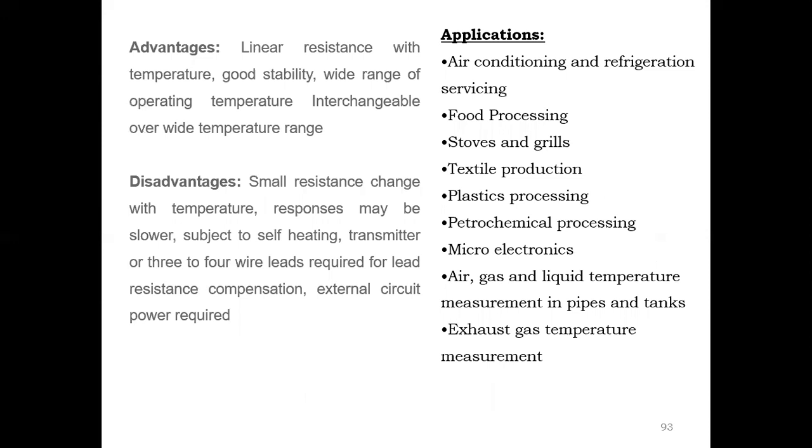Advantages of the RTD: linear resistance with temperature, good stability, wide range of operating temperature, and interchangeability over a wide temperature range. Disadvantages: small resistance changes with temperature, responses may be slower, subject to self-heating, and three or four wire leads are required for lead resistance compensation.